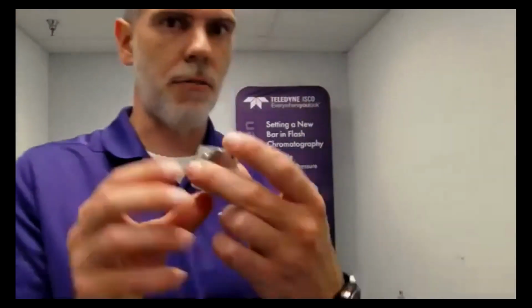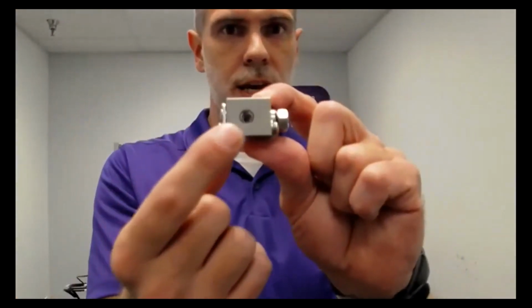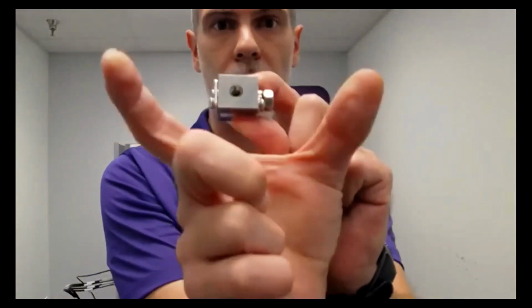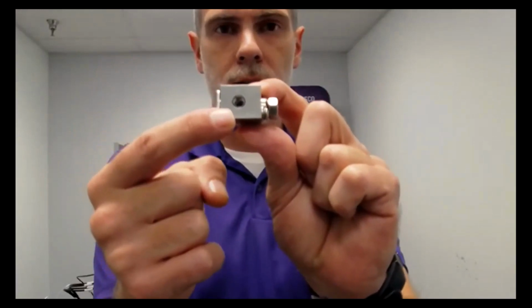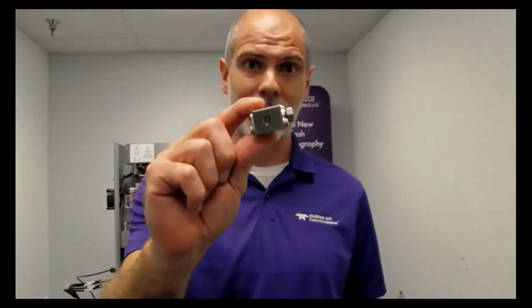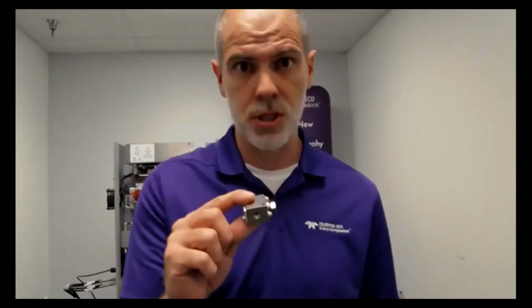Now, I think what Paul's specifically asking is about the rods inside the flow cell itself. Have we seen failure of those? The answer is yes. We see gaps close. We see gaps widen. We see things get stuck in there. Sometimes even you'll have a cracked quartz rod that's inside there. Now, when you have a cracked rod, you may still have good light energy. You may not. But one thing you'll definitely notice is your chromatogram will be crazy. And that's because it's doing a little bit of refraction when you have a crack in there, okay? So I hope that answers your question. If I wasn't specific enough, let me know. But the simple answer is yes. The fiber optics play a huge role in the light detection, and we have seen failures of them. So be aware when you service flow cells, okay?